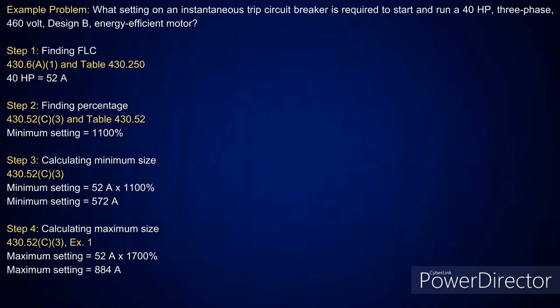Okay. Now, this one is where you're going to look at 430.52(C)(3). The reason is that this is an instantaneous trip circuit breaker. And you'll notice if you look over at Table 430.52, you're going to pick up your instantaneous trip breaker there too. But the only difference is that here we're going to be looking at the maximum. You're going to have a minimum and maximum setting here. There's not going to be a next size. You're doing settings here. And when you look at 430.52(C)(3), it's going to tell you that you can take it up to a maximum of 1,700%, and that'll be a B2B, I think it is, something like that. It's been a while since I've looked at that.